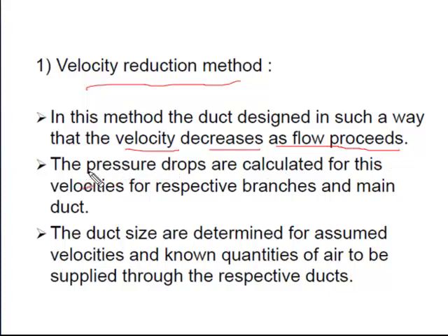Second, the pressure drops are calculated for these velocities for the respective branches of duct and main duct. The duct sizes are determined for assumed velocities and known quantities of air to be supplied through the respective ducts.